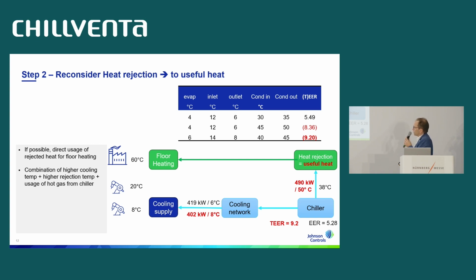Okay, coming to a next step. So reconsider heat rejection. Typically the heat rejection is not used in cooling application, but if you also have a heating demand, for example floor heating, this is useful heat. So again, this is the same system where I changed the numbers of the condensation.